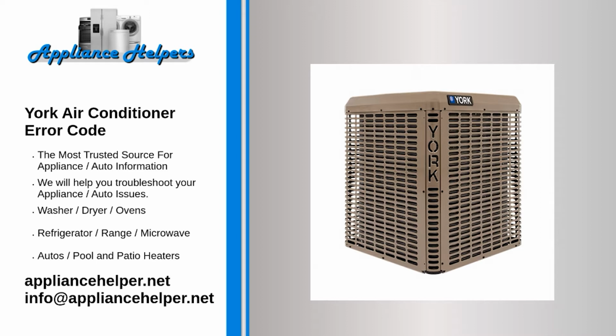Code EC. Problem: Refrigerant leak detection system malfunction. Code EE. Problem: Water level alarm malfunction. Code E8. Problem: Dual indoor unit twin model only communication malfunction. Code E9. Problem: Another twin model malfunction. Code F0. Problem: Overload protection.